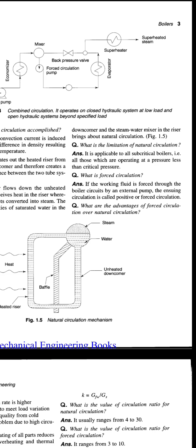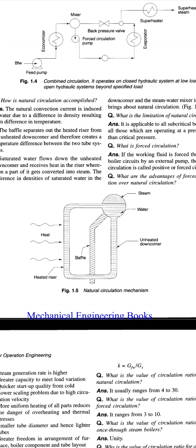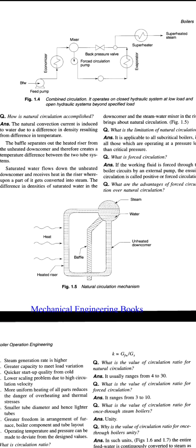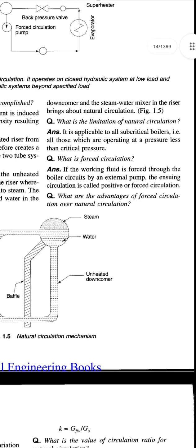We can see the natural circulation in the figure. Heat is going to the heated riser, downcomer is on the right side. So in the steam drum, water is naturally circulating. Baffles are provided in between the upcomer and downcomers. So next question, what is the limitation of the natural circulation? It is applicable to all subcritical boilers, all those which are operating at a pressure less than critical pressure.